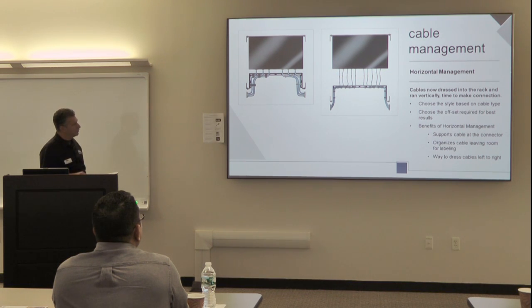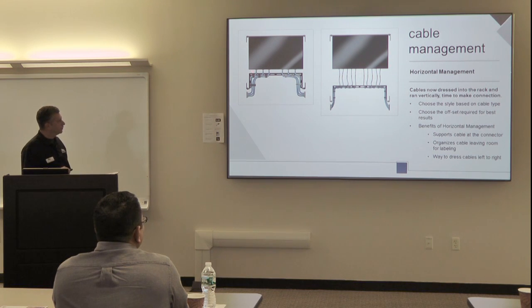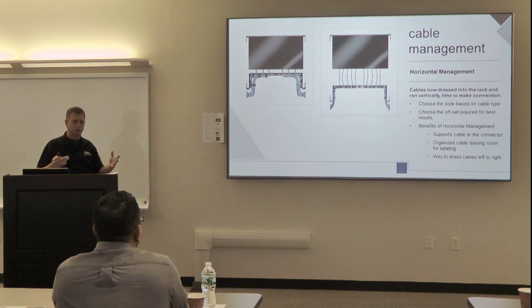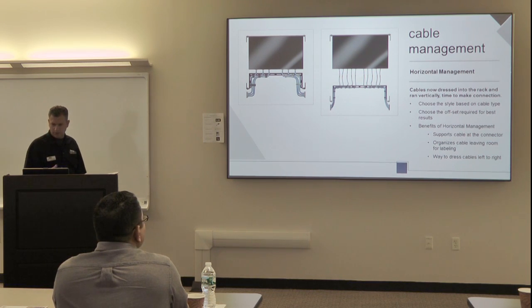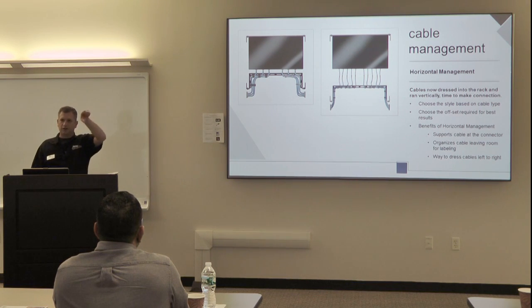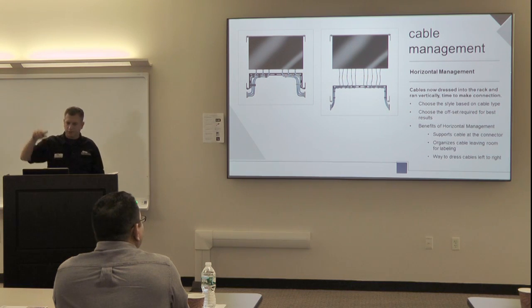Again, you want to label - that follows some of the standards out there. All cable must be labeled. Another thing is keeping it close to the connection, getting that cable nice and tight so it doesn't put pressure on your connector in the back. This organizes things and leaves room for labeling, and it's also a way to dress from left to right. A lot of times you may come up the left side of the rack and need to get to the right - this is a great way to do it, going horizontally across and then up to the equipment.